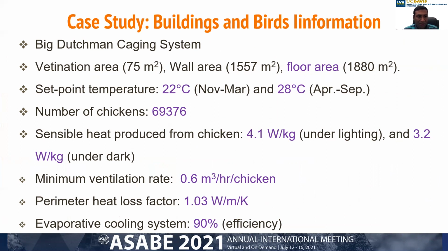We considered a Big Dutchman caging system with a floor area of 1880, with set point temperature of 22 degrees Celsius from November to March and 28 degrees Celsius from April to September. The number of chickens was 69,376, with sensible heat production from the chicken at 4.1 watts per kg during lighting time and 3.2 during the dark period. Minimum ventilation was considered 0.6 to maintain indoor air quality, and evaporative cooling efficiency was considered 90%.